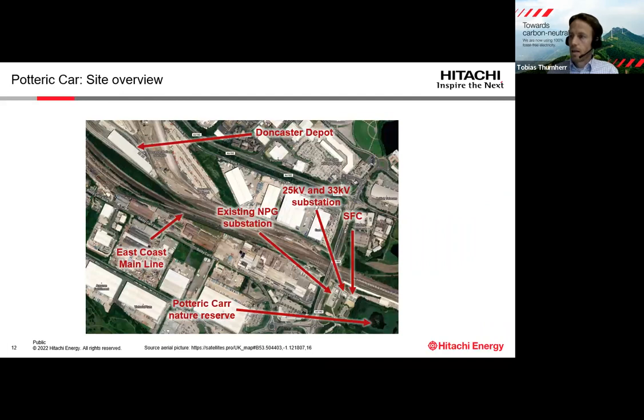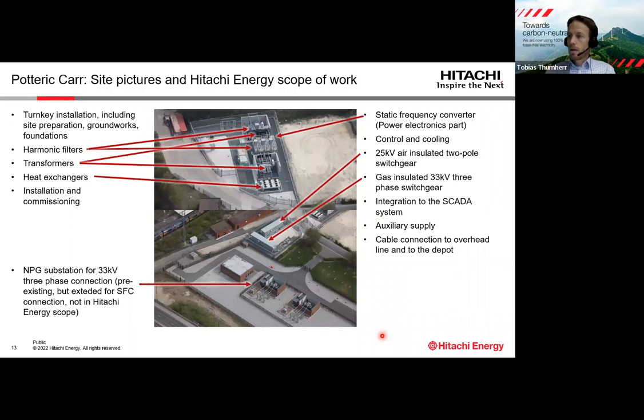Some words about the rail SFC at Potteric Carr, starting with an overview of the site. We have the East Coast Main Line here in the middle. Then the Doncaster depot just next to the railway line. And then there is the SFC located here with a connection to the northern power grid substation, existing 33 kV. Then we have here the 25 kV and 33 kV substation for the static frequency converter, and just next to it the static frequency converter. And close to this static frequency converter location, we have the Potteric Carr nature reserve. Here you see a little bit a closer view of the static frequency converter and the connection.